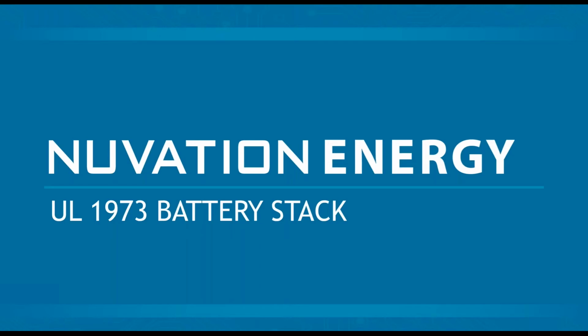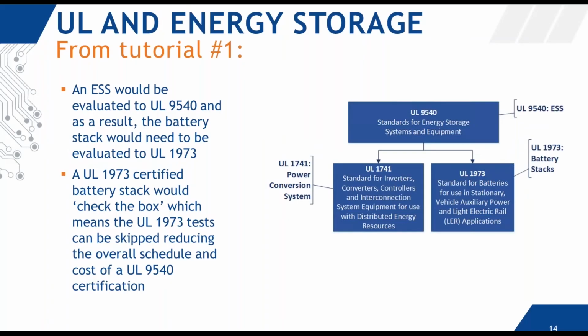So let's dive into what it means to have a UL 1973 recognized or certified battery stack. And just carrying over from tutorial 1, because we briefly introduced this concept, a high-level ESS would be evaluated to 9540, and as a result, those battery stacks that are in there would have to be evaluated to 1973 as well. So a 1973 certified stack, if you already had that, would just check the box. So if you were to submit for a UL 9540 evaluation, what that would look like is they would get to this section, they would see that you're using a 1973 certified stack, and they would check the box. So that reduces a lot of test time and cost because you don't have to go through that with the stack that you brought. And so as we can already see from this simple diagram, there's a hierarchical approach when it comes to these types of standards. And so 9540 will call out 1741 for power conversion systems and 1973 for stacks.